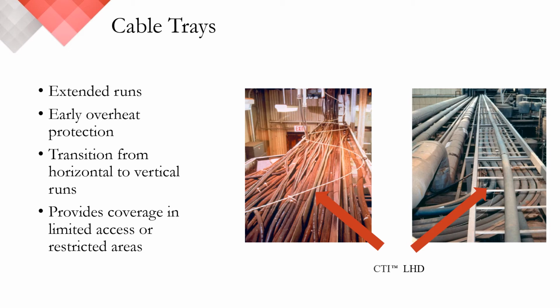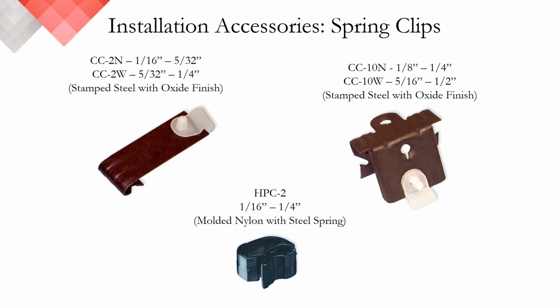Because of the unique shape and design, we can bring the linear heat detection as close to the areas being protected as needed or wanted. I also want to note the manner in which the detector is installed. Due to the nature and construction of linear heat, you must maintain a bend radius of 2.5 inches. Bends tighter than this run the risk of compromising the integrity of the heat-sensitive polymers. In this example, we see sweeping arcs traversing the cable tray. This can be installed both horizontally and vertically. It's required to support the linear heat detector every 5 feet.